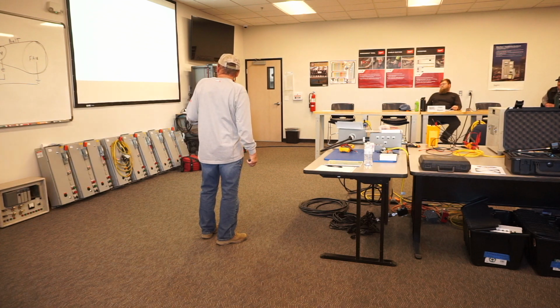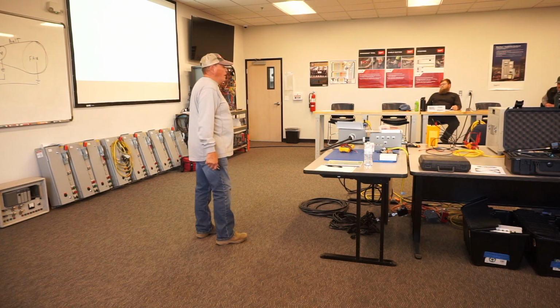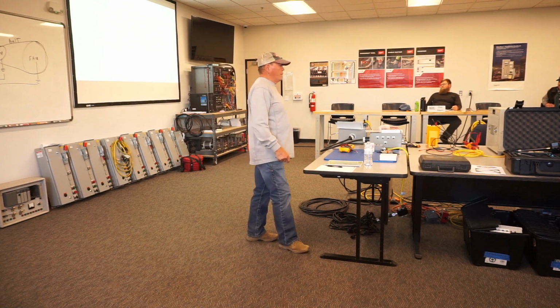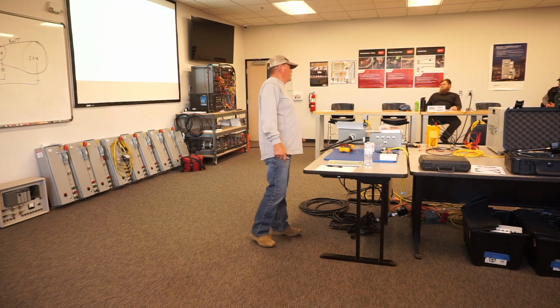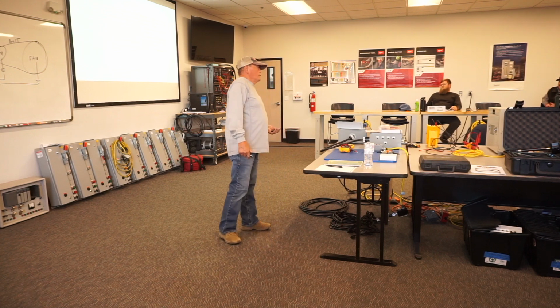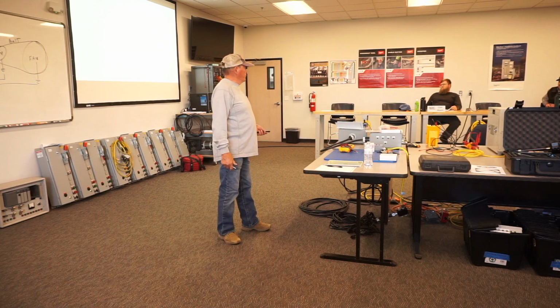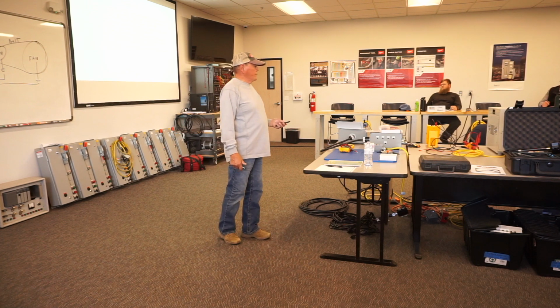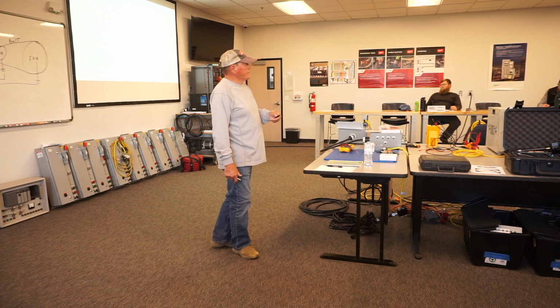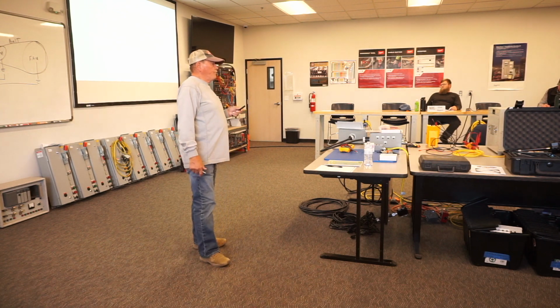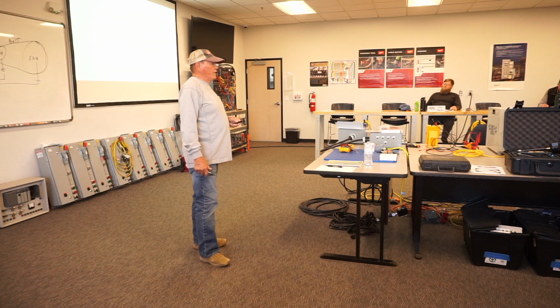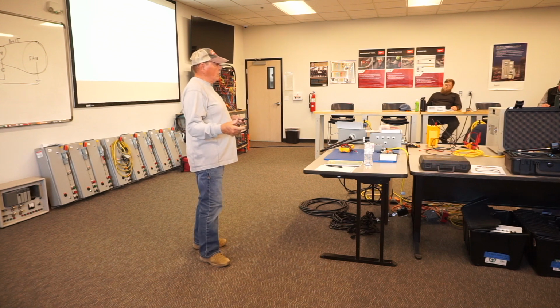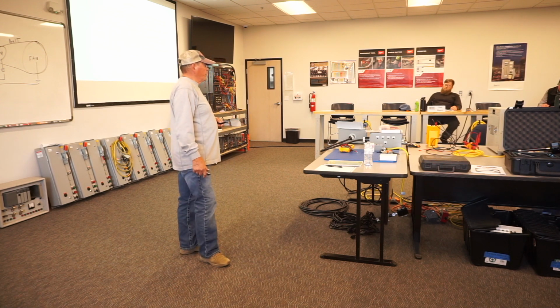Now, we talk about the 7th harmonic. A harmonic is simply a multiplier of the fundamental being 60 hertz. So, the first harmonic is 60 hertz, the fundamental. The second harmonic, double that. The third harmonic, triple that, right? So the third harmonic, 180, the fifth, 300, the seventh, on and on and on. Drives put out primarily 5th and 7th harmonics. That's the majority of harmonics coming off of drives. There's a lot of others, but they're in smaller magnitude, but generates 5th and 7th.